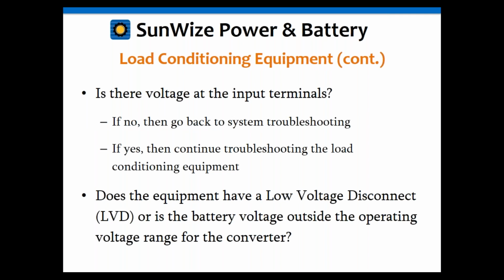One of the simplest things is: is there voltage at the input terminals? If there is, then obviously let's continue on. If there isn't, then go back and find out why. Again, you may have gone into low voltage disconnect that we talked about earlier, something like that. It could be a circuit breaker trip for some odd reason. Maybe the inverter had some type of surge on it that overloaded the breaker and tripped it. So you might want to go back and troubleshoot and find out why there's no voltage at the input terminals to the converter or inverter.